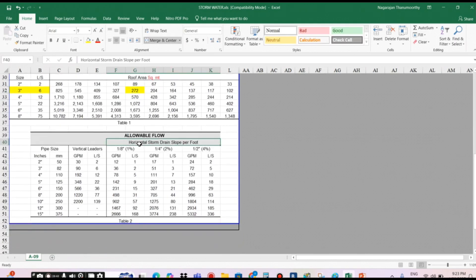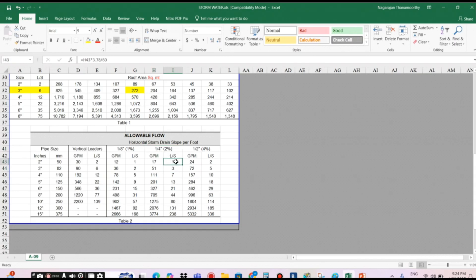For the horizontal piping, there is another table, similar to the drain edge piping table. You need to specify the percentage slope of the horizontal piping — let's say 2 percent slope. First, determine the flow rate. For example, a pipe carrying 2.03 liters per second: on the table, between 1 liter per second and 3 liters per second, that point falls here. Moving across to the vertical leader column, it shows the vertical leader can hold up to 6 liters per second.